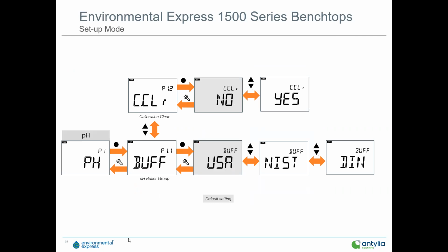So next, again, from the pH on the last page, you'd hit the enter button. You go in and pick your buffer set, whether it's USA, NIST, or DIN. And then to reverse out of that, you just hit the settings button. From the buffer sub-program, you can go up and clear data. The default settings here are in gray, USA buffer, no to clearing data.